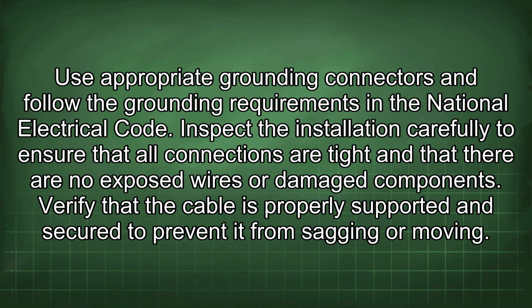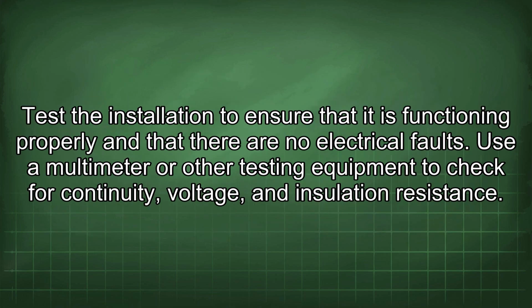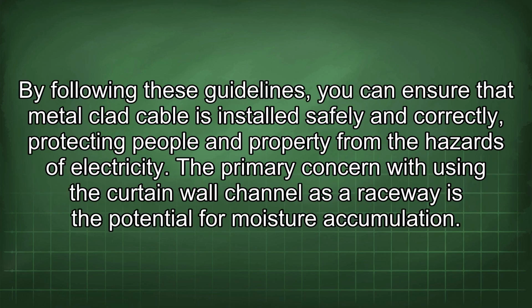Inspect the installation carefully to ensure that all connections are tight and that there are no exposed wires or damaged components. Verify that the cable is properly supported and secure to prevent it from sagging or moving. Test the installation to ensure that it is functioning properly and that there are no electrical faults. Use a multimeter or other testing equipment to check for continuity, voltage, and insulation resistance. By following these guidelines, you can ensure that metal-clad cable is installed safely and correctly, protecting people and property from the hazards of electricity.